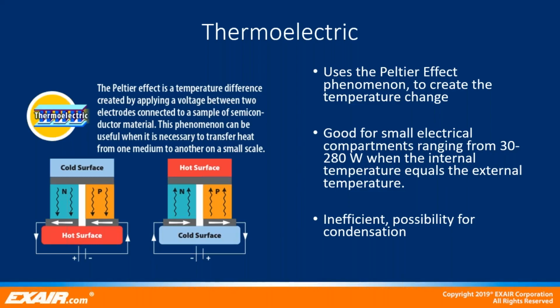Thermoelectric. The underlying phenomenon behind thermoelectric cooling systems is known as the Peltier effect. This effect is harnessed by using two elements of a semiconductor material upon application of a direct current, DC power source. The device transfers heat from one side to another. The side the heat is taken from becomes cold, and fans blow air against the cold surface, distributing cold air around the cabinet. The major disadvantage to the Peltier effect is that it's inefficient. The flowing current itself tends to generate a significant amount of heat, which then gets added to the overall heat dissipation needs.